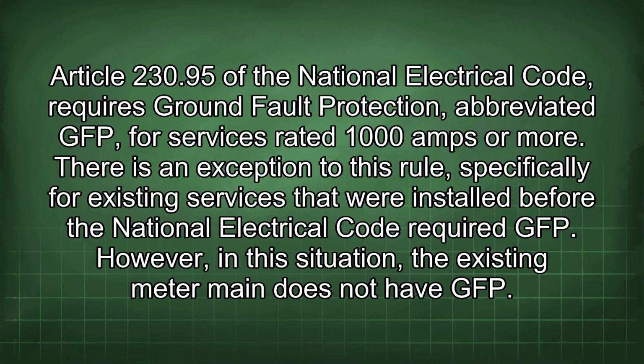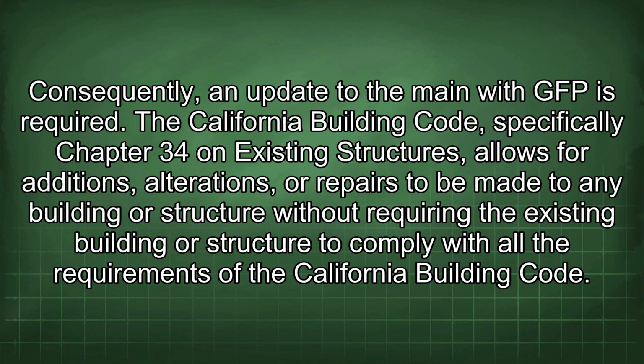Article 230.95 of the National Electrical Code requires ground fault protection, abbreviated GFP, for services rated 1000 amps or more. There is an exception to this rule, specifically for existing services that were installed before the National Electrical Code required GFP. However, in this situation, the existing meter main does not have GFP. Consequently, an update to the main with GFP is required.